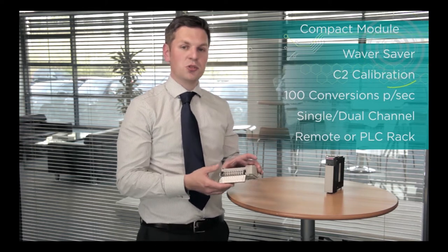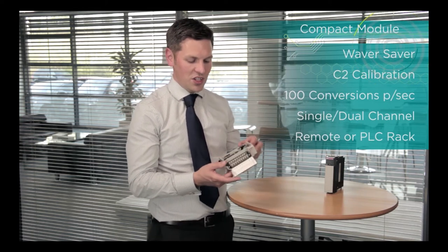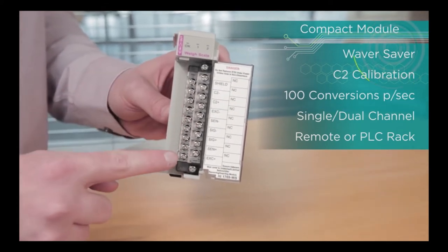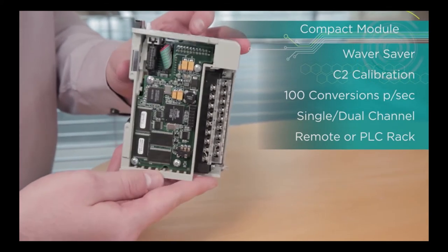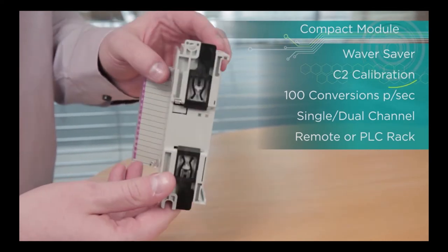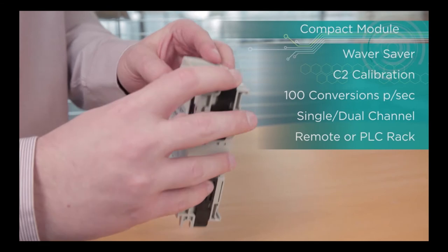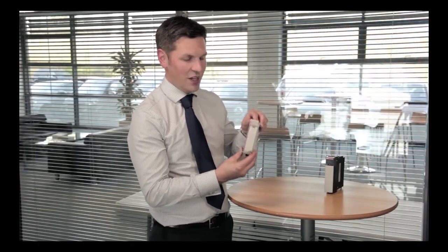This one does 100 conversions a second and it's actually available in two different formats. You can get one with one set of inputs for a load cell or one with two. This is one we commonly use in Compact Logix and it can be used in a remote rack if you want to, or in a PLC rack.